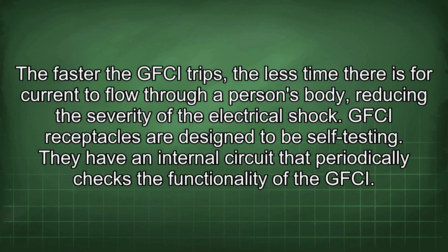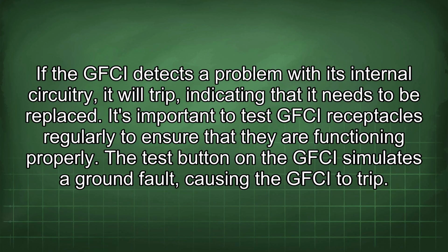GFCI receptacles are designed to be self-testing. They have an internal circuit that periodically checks the functionality of the GFCI. If the GFCI detects a problem with its internal circuitry, it will trip, indicating that it needs to be replaced.